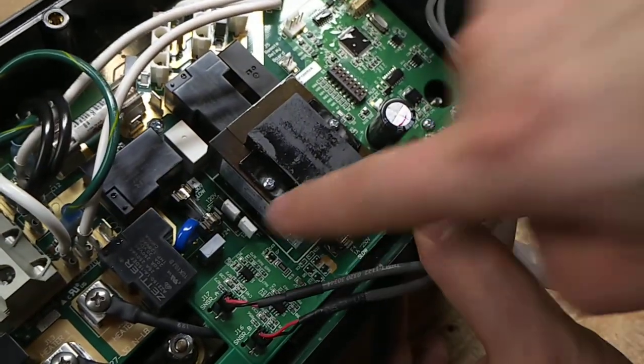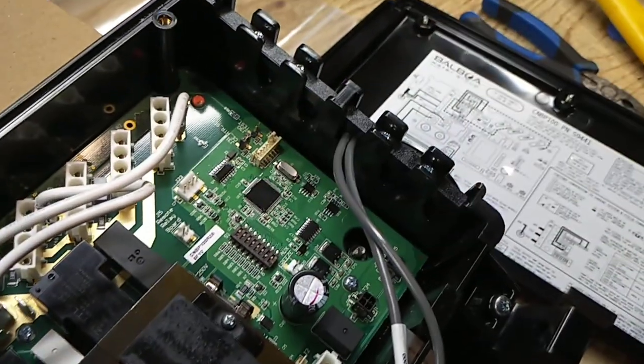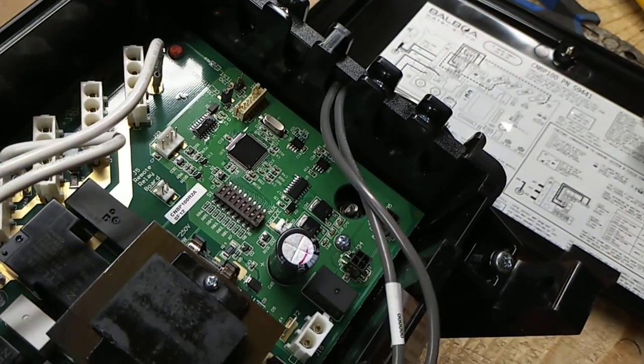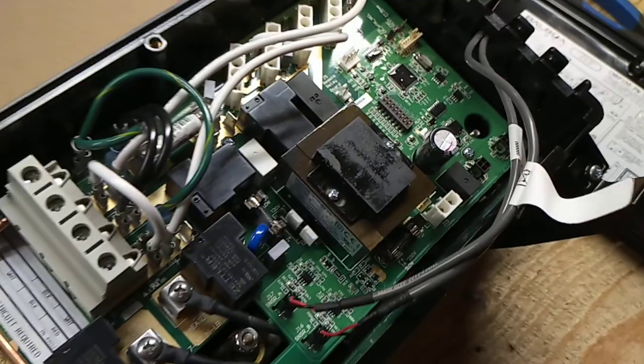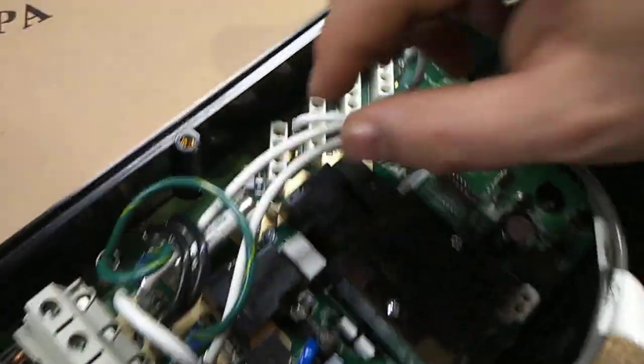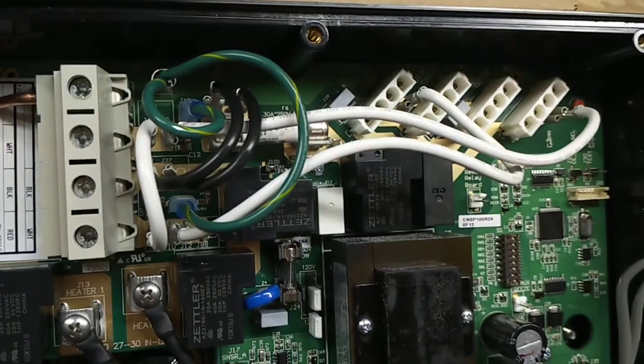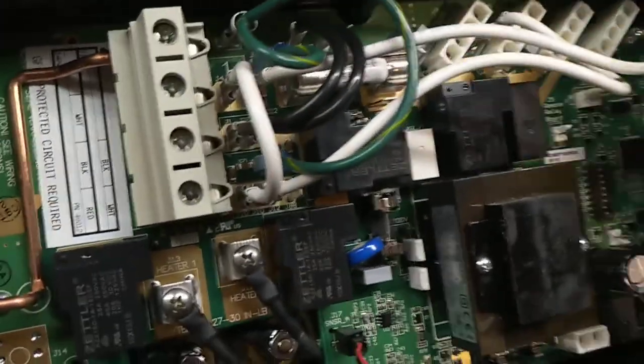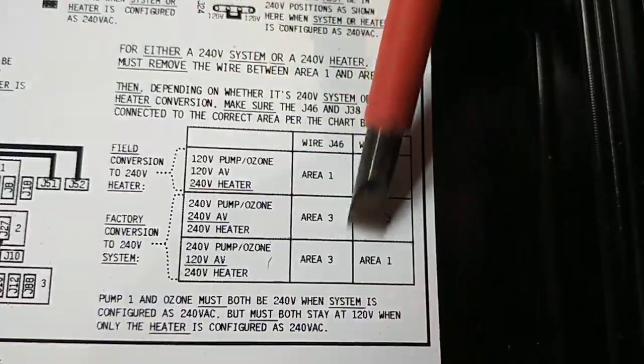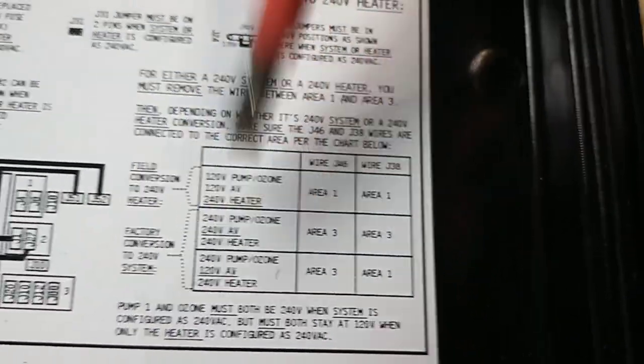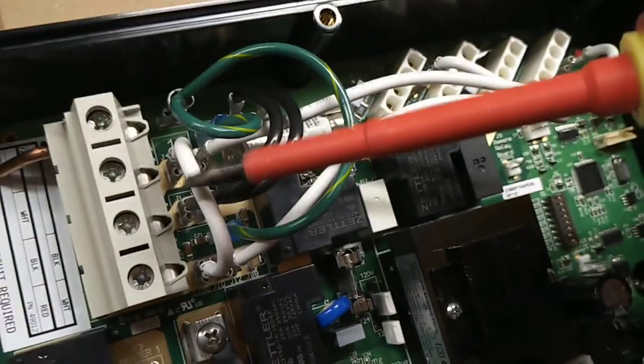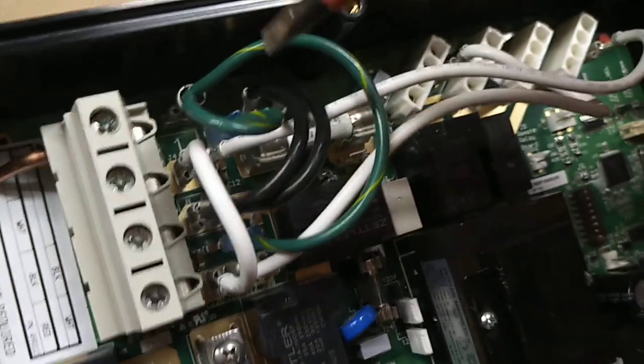So we've adjusted the fuse. We've adjusted these 120 volt jumpers. We've adjusted the J31 jumper. We've adjusted the dip switches here. And the last thing we need to look at is the power going into the pump and banks one and three. And this is referenced, just if you need further reference, right here in this section. So what we're going to do first is you need to remove the jumper wire that's connecting bank number one.